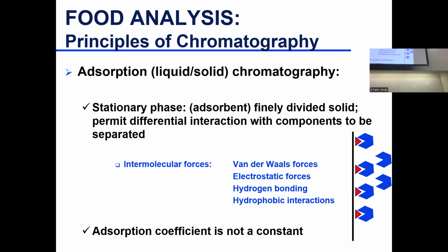Okay, so you will see a peak here that's big, and then you will see another peak of the same compound because you injected too much. Some of it did not have a chance to interact, left the column right away, and some interacts and comes out. So you have something called split peak. Incorrect. Wrong. You don't want that to happen.